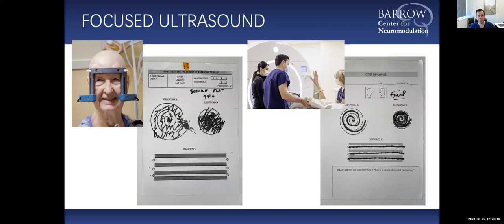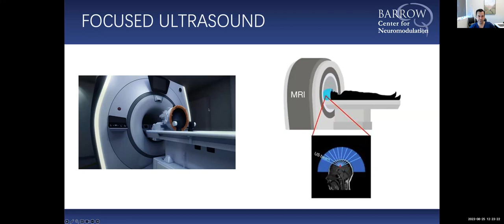So there's the MR scanner in the back here on the left, and this is the helmet. This helmet is placed over the patient. The patient actually has a plastic band placed over their head, and their head is being cooled by cold water throughout the operation. So this blue can be considered cold water to help cool things as energy is being delivered. So it's the 2 components: the MRI scanner that can measure temperature, not just take pictures, and then the helmet that delivers the ultrasound energy.